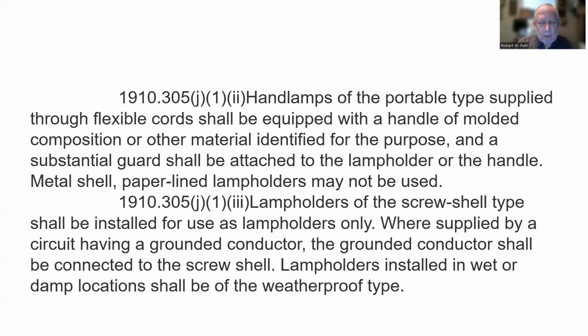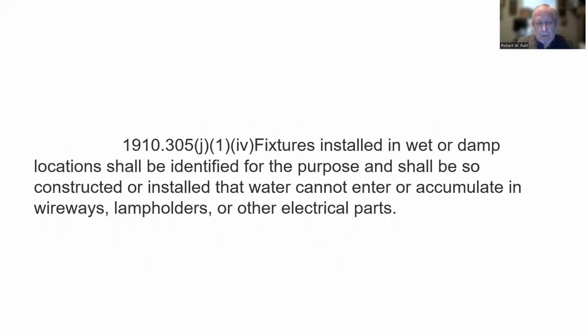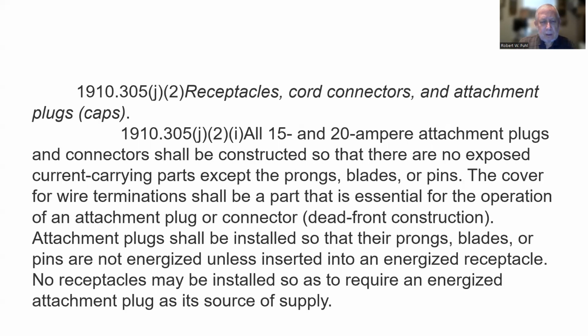Lamp holders of the screw shell type shall be installed for the use as lamp holders only. Where supplied by a circuit having a grounded conductor, the grounded conductor shall be connected to the screw shell. Lamp holders installed in wet or damp locations shall be of the weatherproof type. Fixtures installed in wet or damp locations shall be identified for the purpose and shall be so constructed or installed that water cannot enter or accumulate in wireways, lamp holders, or other electrical parts.